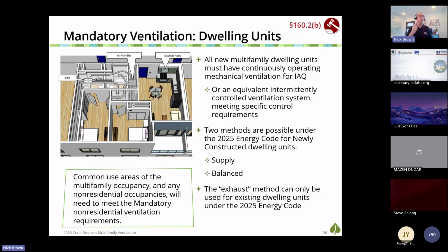So there's two methods permissible now in new multifamily buildings, supply and balance ventilation. Exhaust can only be used for altered existing dwelling units under the 25 code, and as Jorge points out, single family. Common use areas are treated like non-residential zones, and those will need to meet their own mandatory ventilation requirements, which we'll cover in the second half today.